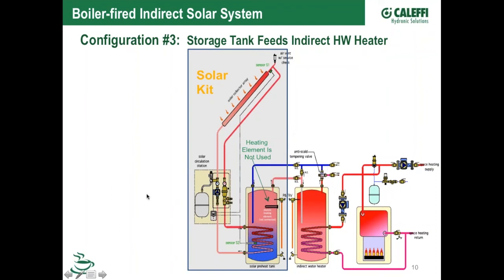of the heat there. So, you know, you don't really want to dump heat, because that's heat that, quote unquote, was free energy that you got. And then if you're running a pump to get rid of it, you're kind of going the wrong way on your financials here. Running the pump to get rid of free heat doesn't pencil out so well. But yeah, so we can help you with that. If you do have a job where you've had problems with them overheating, your glycol's breaking down, we can talk you through how to enable those functions, how to set them up, how to use those. That can buy you a little bit of wiggle room for overheat protection. All of our controls have those functions in them, by the way.